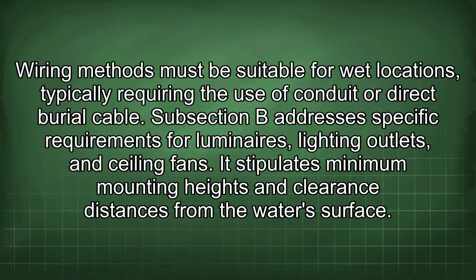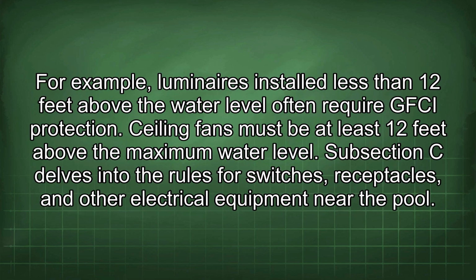Subsection B addresses specific requirements for luminaires, lighting outlets, and ceiling fans. It stipulates minimum mounting heights and clearance distances from the water's surface. For example, luminaires installed less than 12 feet above the water level often require GFCI protection. Ceiling fans must be at least 12 feet above the maximum water level.